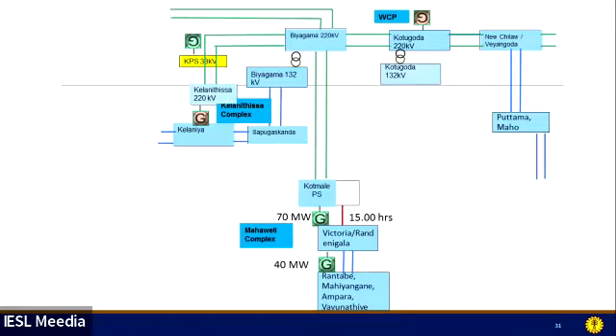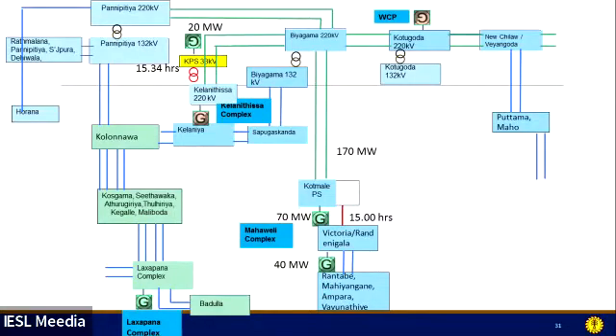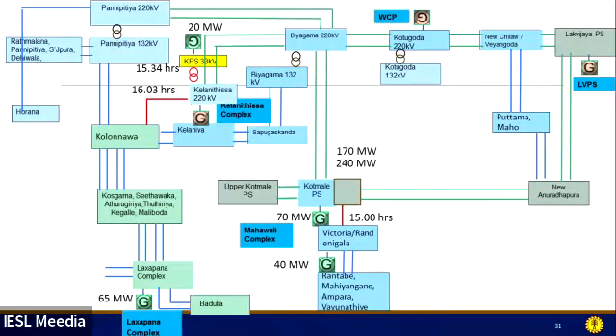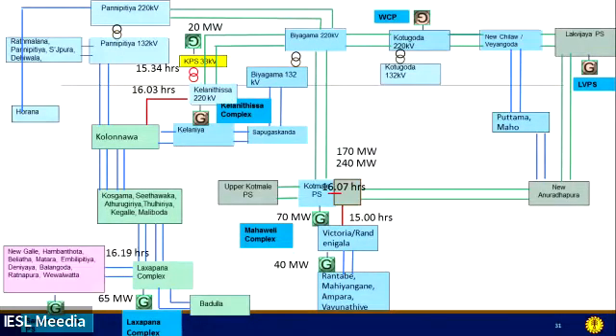At the same time, from the Kelanitissa small generators, the Colombo supply was being restored, and that was synchronized with this system through the Kelanitissa inter-bus transformers at 1534. The load at that time was 170 megawatts in Mahaweli and 20 megawatts in Kelanitissa. Then the Laxapana system was restoring in parallel to these incidents. Laxapana and the rest of the system were synchronized at 1603 hours. But at that time, the Laxapana generation was 65 and the Mahaweli or rest of the system load was 240. Then from Upper Kotmale, we extended the supply to Lakvijaya via New Anuradhapura, and that system was synchronized with the rest of the system at 1607.